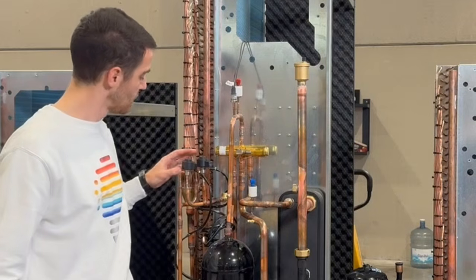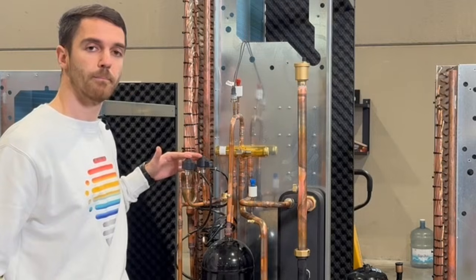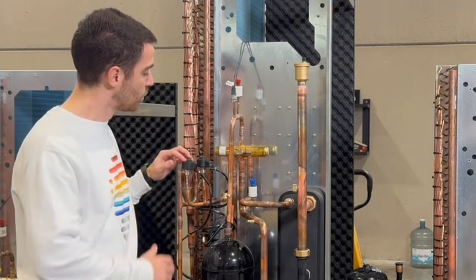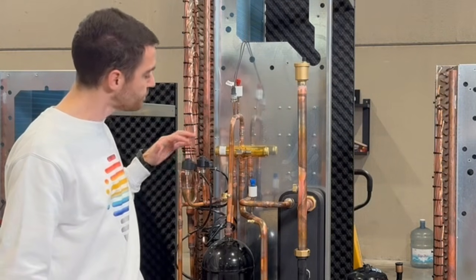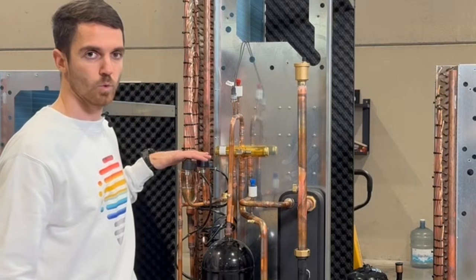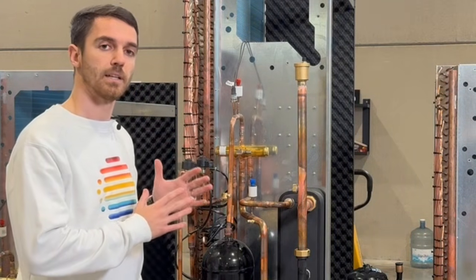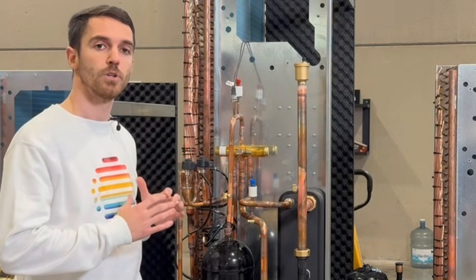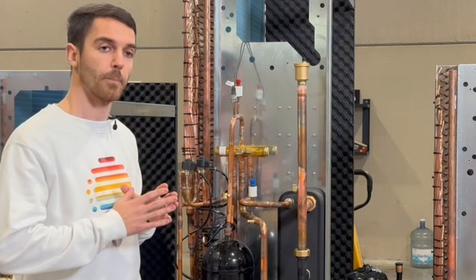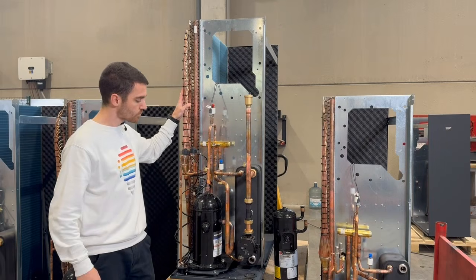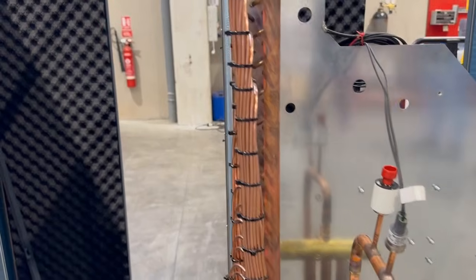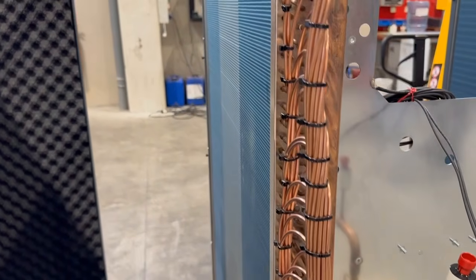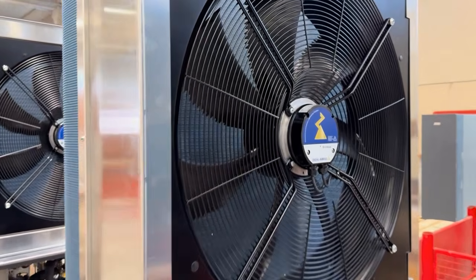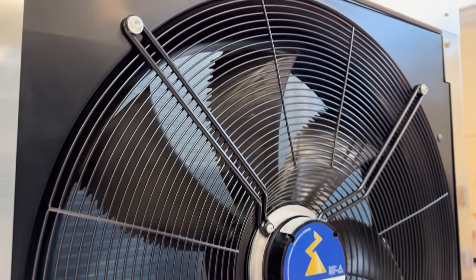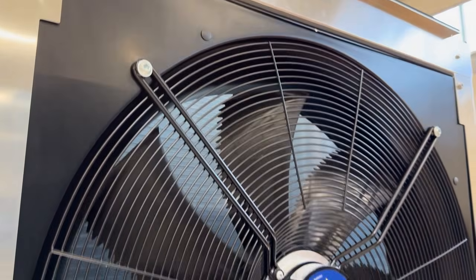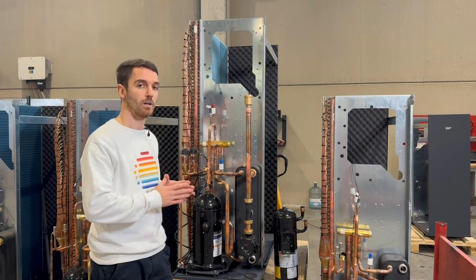2 expansion valves. So this is important because you can manage refrigerant cycle quite good when you have 2 expansion valves. Usually there is only one. In cooling and in low temperature in heating, you can manage refrigerant temperature so you don't have so high capacity drop. Evaporator, which is not usual that you have evaporator on the front side, and on the back side here it's fan. So really low noise level, because usually noise is always coming from the fan.